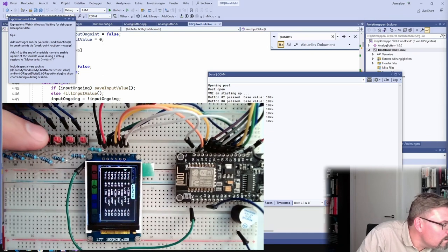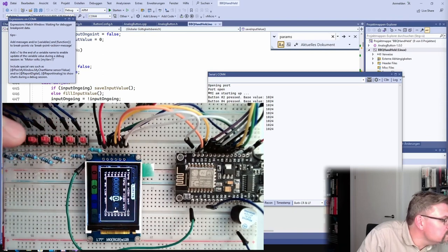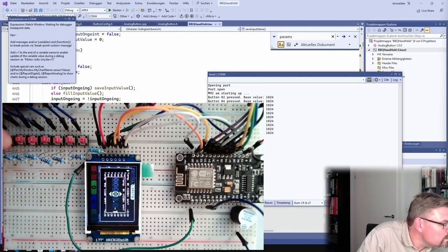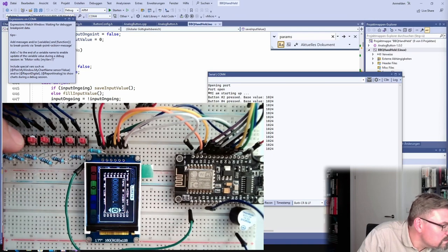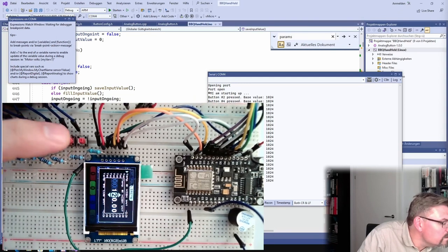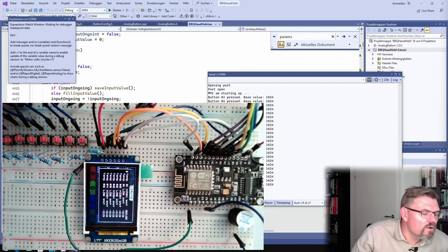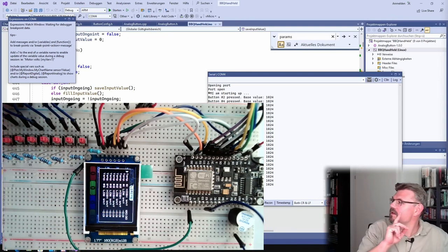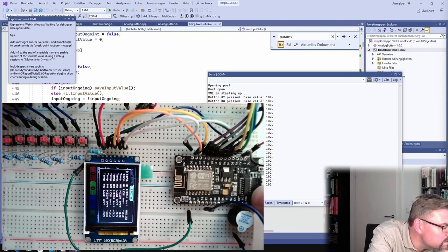And now, let's set this. Input high. Okay, it's looking good. This input I have to fix. High limit shall be 120. Yes, it's stored. Okay, and now let's try if it is still stored. If I press the reset button, reset to this, yes.